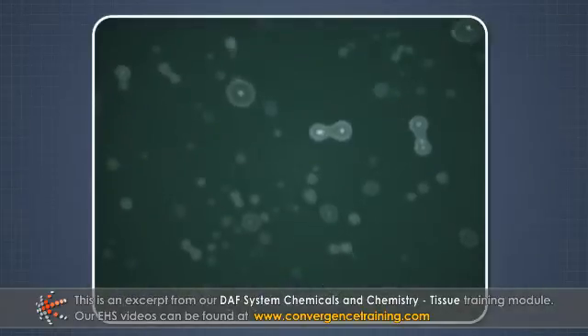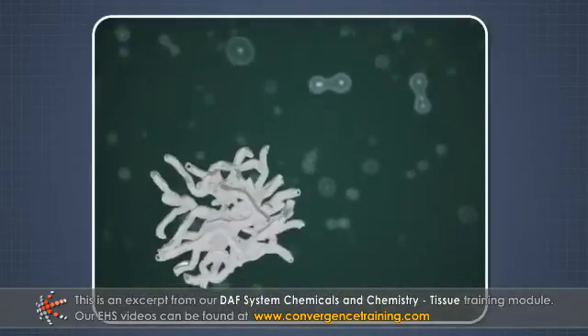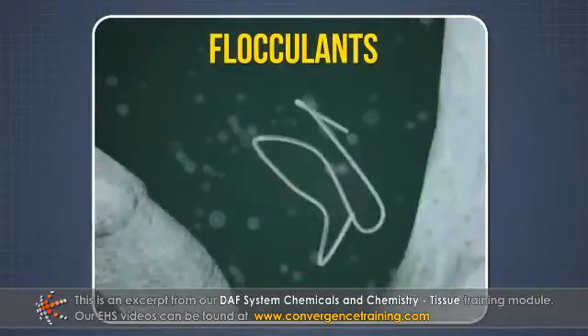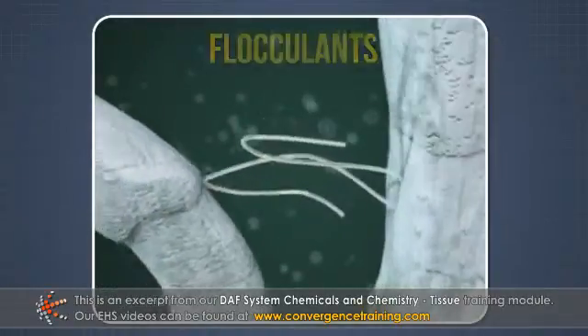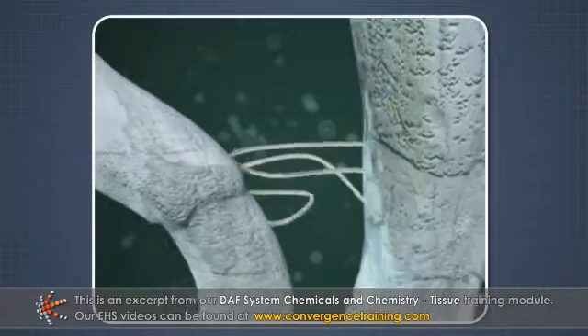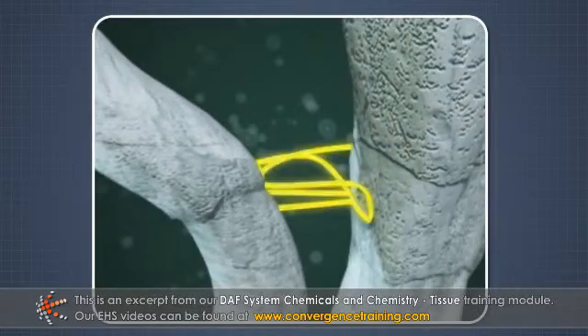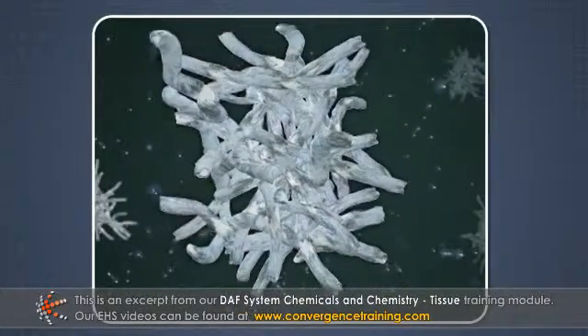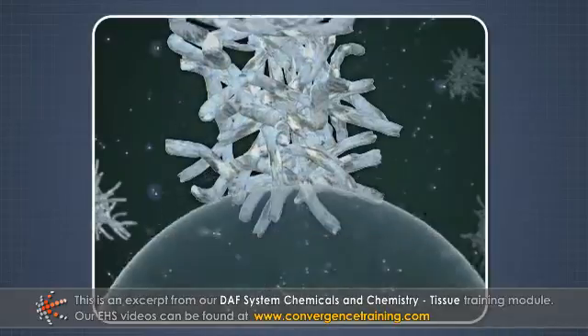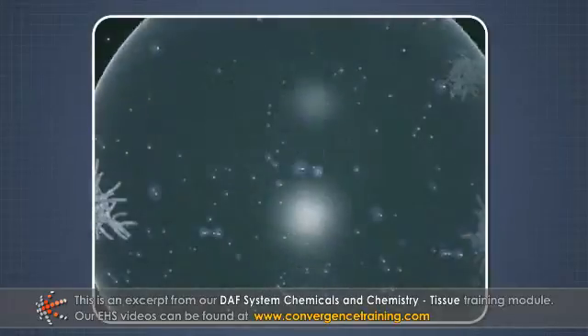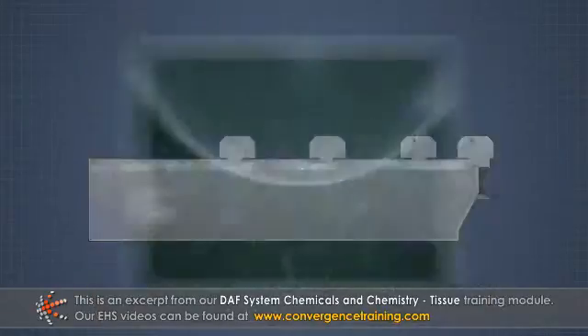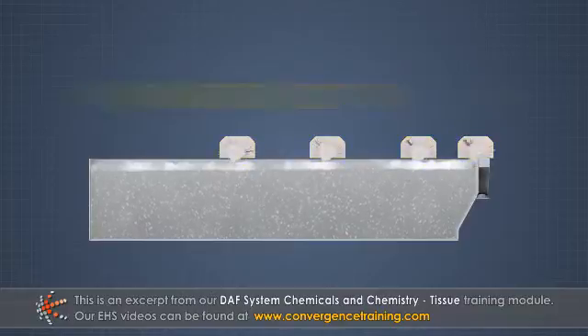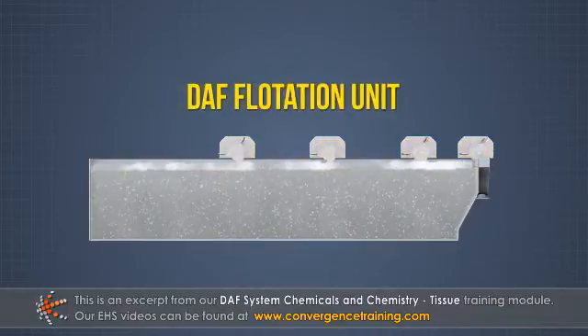High molecular weight polymers called flocculants are added to the solution to help bridge, bind, and strengthen the floc. These larger floc are more buoyant and easier to float. Once they have reached a sufficient size, they can be skimmed off the surface of the DAF flotation unit.